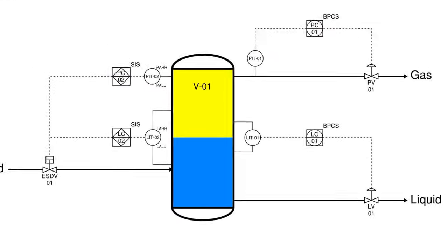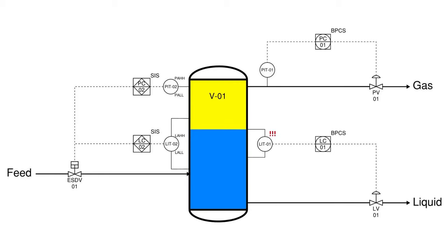If the level increases and is higher than the desired setpoint of the controller, then LC-1 will send the signal which will cause LV-1 to open more, allowing more liquid to flow out of V-1.